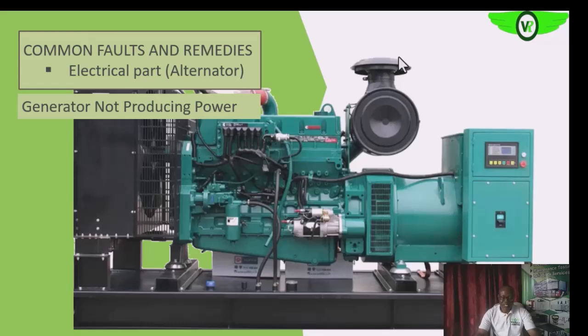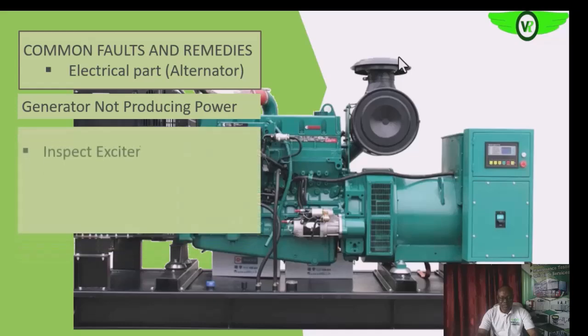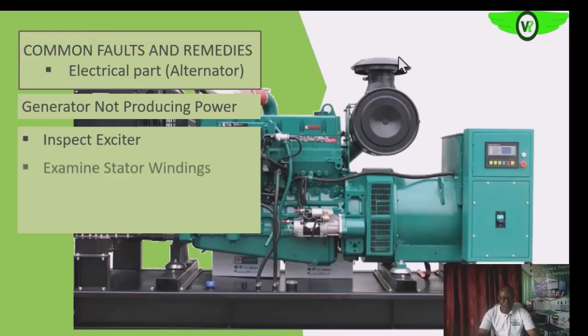When the generator is not producing enough power, a possible cause is that the exciter has failed. If any part of the excitation system has failed, power will not be delivered to the main field, and that will affect the generator entirely — it will not produce.